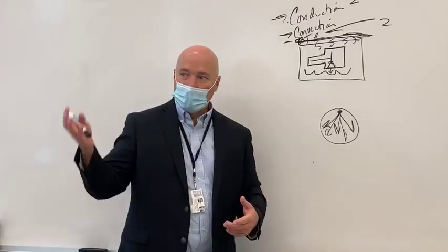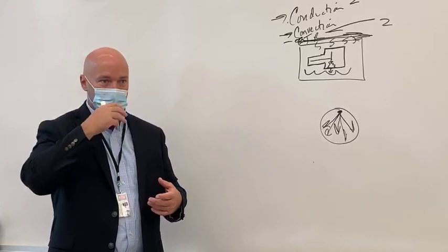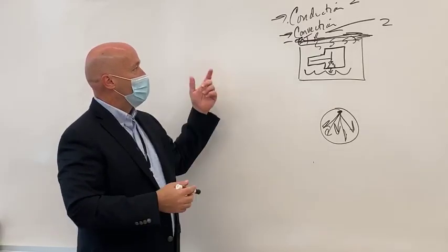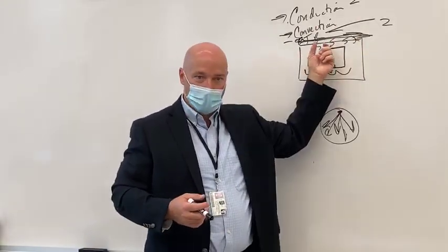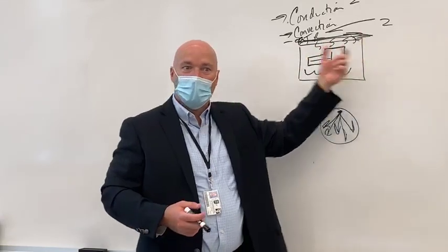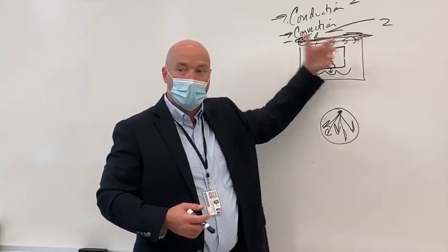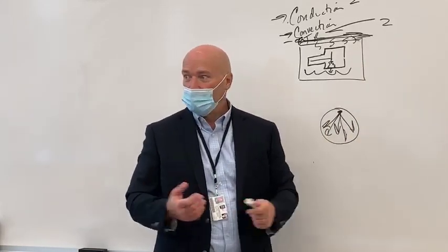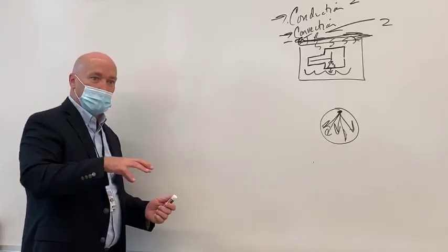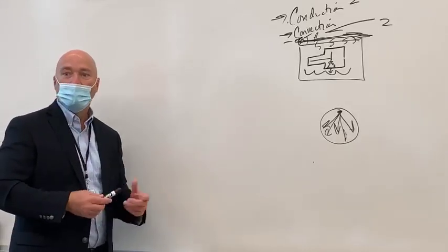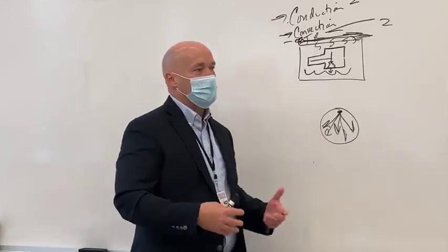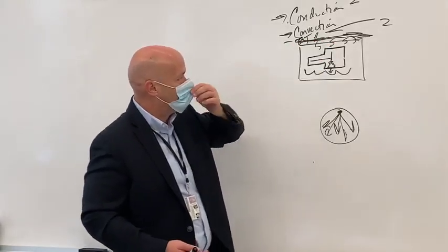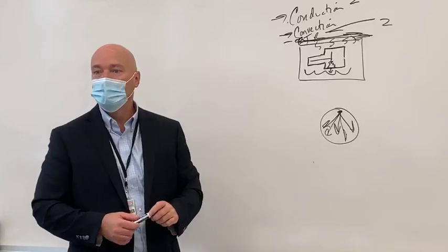Because if you're working in a trauma room, y'all been inside of a trauma room, right? It's like 90 degrees inside there. So with convection, what you get is drawing of air from the room to blow across the oil, right? So if it's cool in a room, do you suppose that would cool the oil down quicker than if it's 90 degrees in a room? It should, right? Cooler air is going to cool the tube down quicker than hot air. So a lot of different things can affect it, but the question was, where do we deal with it? And we deal with it inside of the protective housing in those three different ways. Okay.